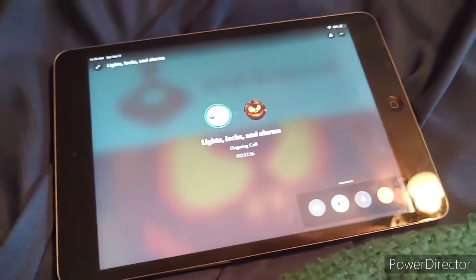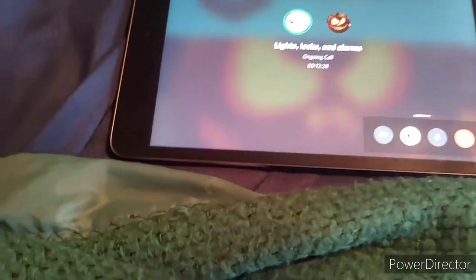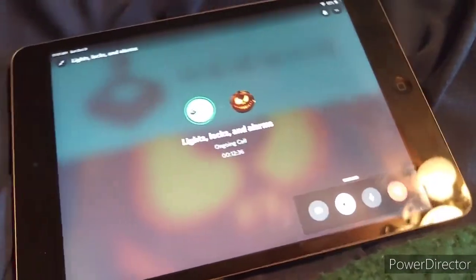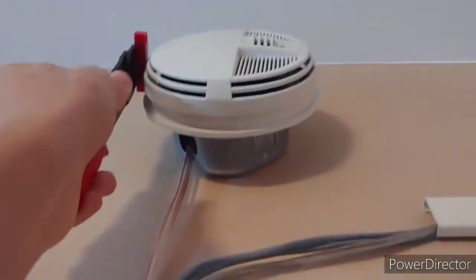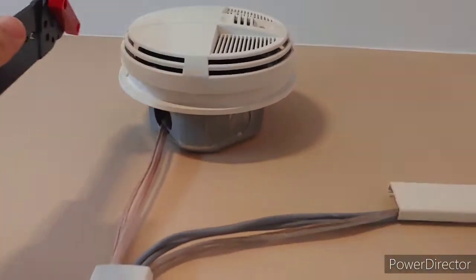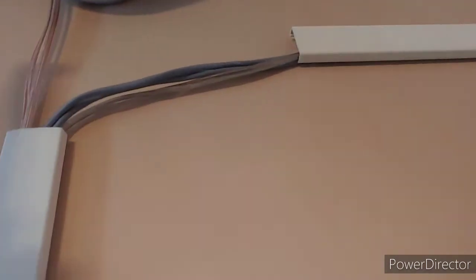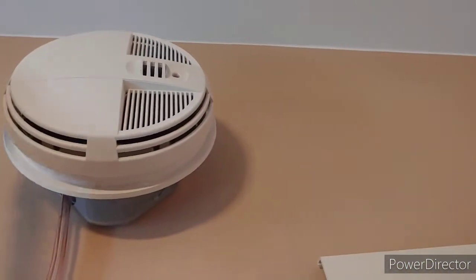What alarm should we activate second? Obviously the system has to reset, so it won't be re-alarming — it'll just be another pull station or smoke detector. Do a smoke detector? I don't care which one — I'm gonna go with the crappy one. Actually, do I have a step stool in here? No, I don't. Well, that's great. I'll try and see if I'm tall enough to magnet test the GE one. I stuck a magnet to my wire strippers, so we're just gonna go ahead and see if I can reach it. Got it — there we go.